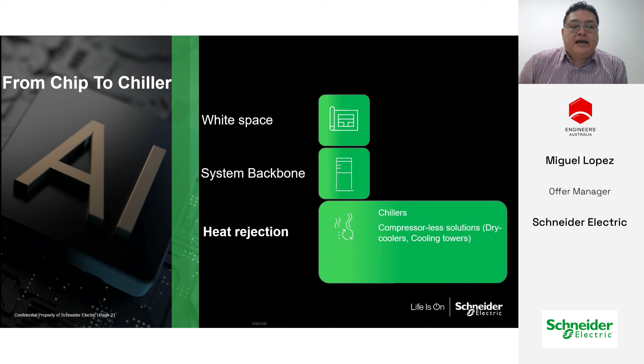And last but not least, moving along to the outdoor heat rejection systems. Once again, a picture tells 1,000 words. You will have the opportunity to review these slides in detail when you get a copy of them. And once again, this information is available through the ASHRAE Technical Committee 9.9. But this slide is just showcasing the multiple reference designs. Now, one thing that Schneider is quite good at, all you need to do, jump onto Google, type in Schneider Electric reference designs for liquid cooling systems, and this information will be available to you, showcasing segregated water loops between your CRAHs and air conditioning systems, to having a discrete heat rejection system for your CDU, which is the left-hand side. The middle of your slide here is showing one single outdoor unit catering for both the CDU heat rejection needs and your CRAH air conditioning heat rejection needs.